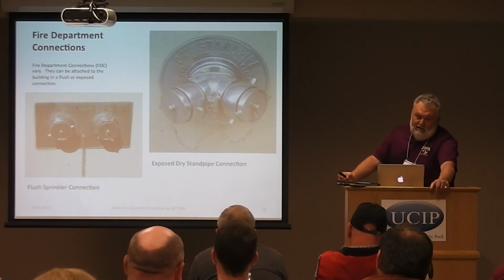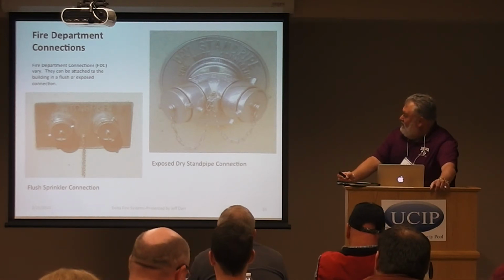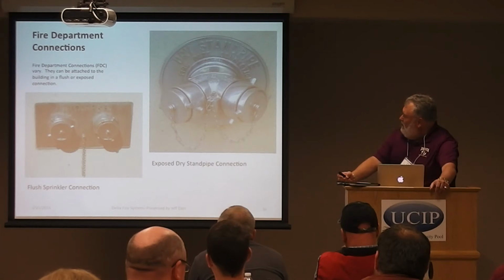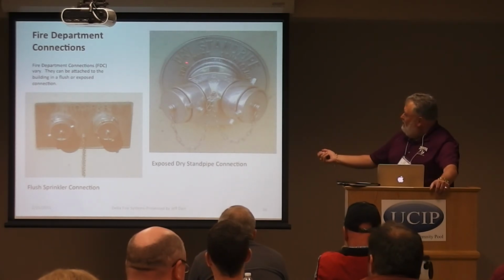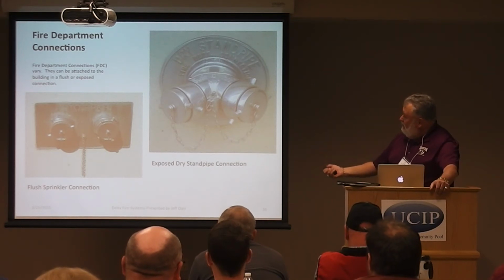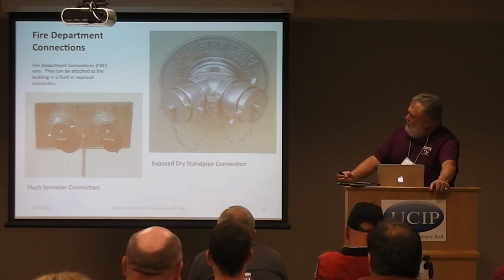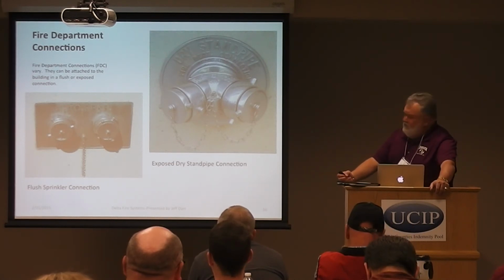So, here are some common things on fire department connections. Now, they can either be located on the building itself. The one on the right is a dry standpipe system. You can see that it tells you right here what they are. This tells you it's an automatic sprinkler system. A flush mount versus an exposed dry system, or exposed connection.